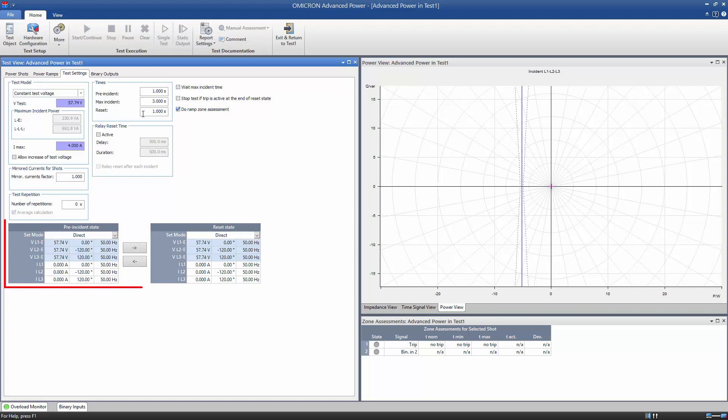At the bottom of the Test Settings tab, define the output values for both the Pre-Incident and the Reset state. It is important to ensure that the currents and voltages in both states are not within the trip range.